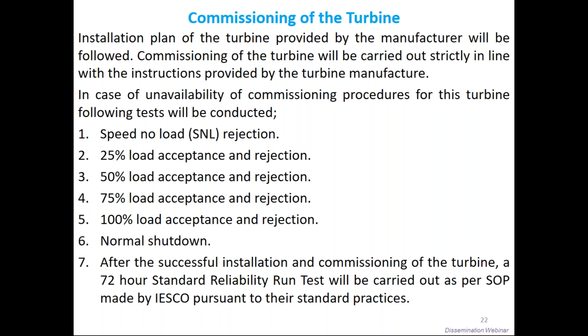And number 7 is, after the successful installation and commissioning of the turbine, a 72-hour standard reliability run test will be carried out as per SOP made by IESCO pursuant to their standard practices. Now we will see what it is actually. For this test, the whole system will be operated continuously for 72 hours, and all critical parameters mentioned in the table we will see in the next slide, means voltage, current, power factor, power, frequency, RPM, stator winding, temperature, etc.